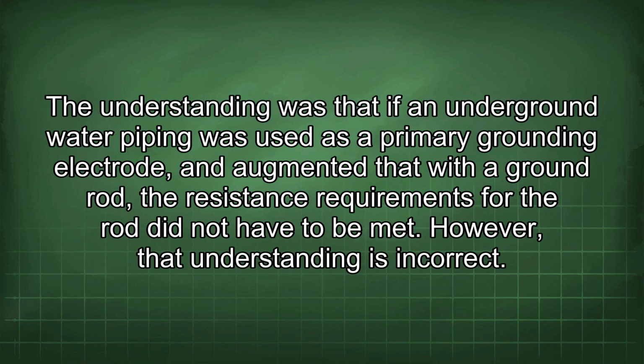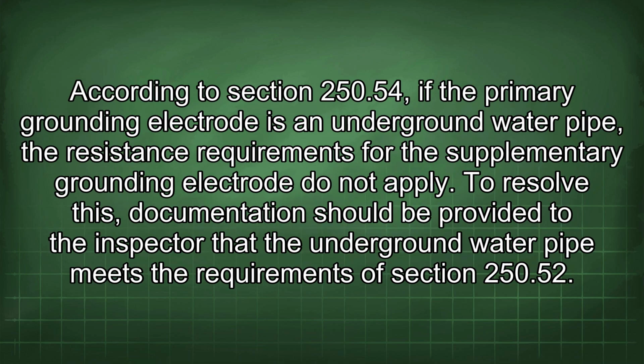The understanding was that if an underground water piping was used as a primary grounding electrode and augmented with a ground rod, the resistance requirements for the rod did not have to be met. However, that understanding is incorrect. According to Section 250.54, if the primary grounding electrode is an underground water pipe, the resistance requirements for the supplementary grounding electrode do not apply.